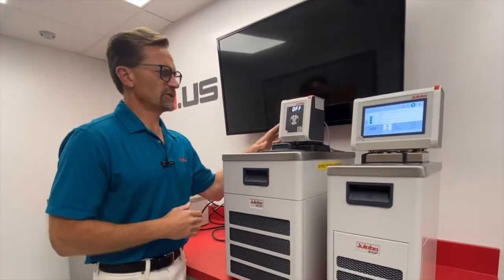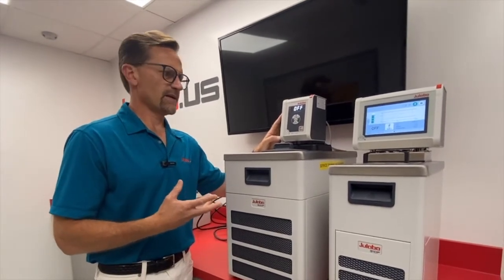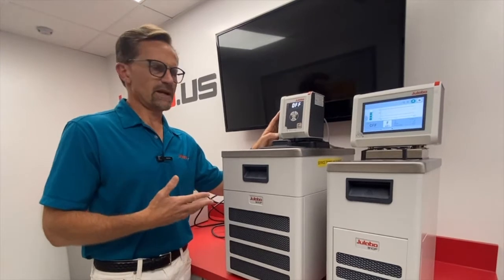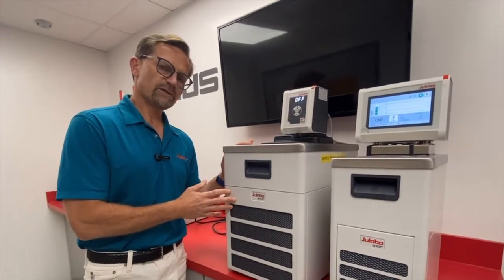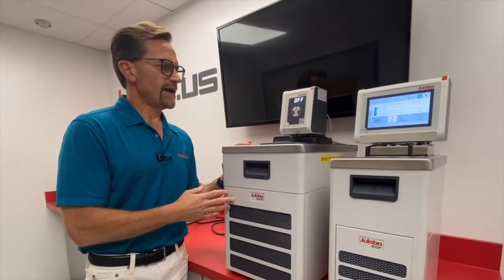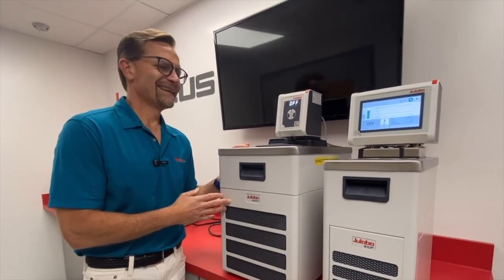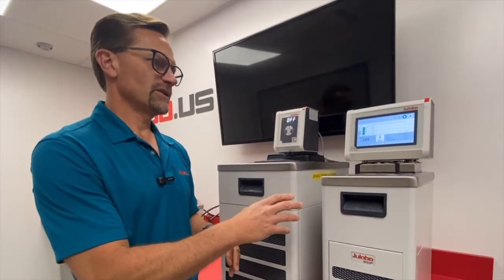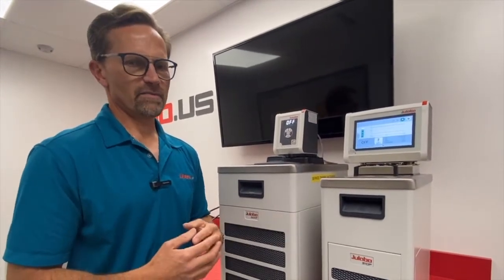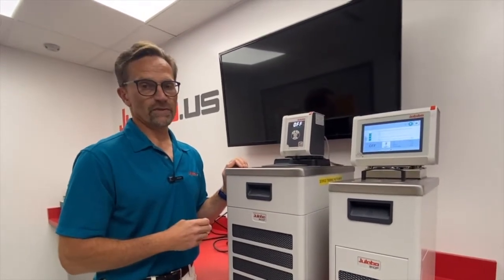From a temperature stability perspective, the Corio CP models in heating circulator combinations have a temperature stability of plus or minus 0.02 degrees C. When paired with a refrigeration unit for heating and cooling, they have a temperature stability of plus or minus 0.03 degrees C. All Magio circulators have plus or minus 0.01 degrees C, with calibration of one, two, or ten-point capabilities, whereas the Corio CP offers either a one, two, or three-point calibration.